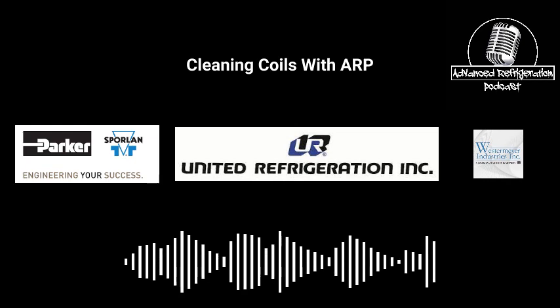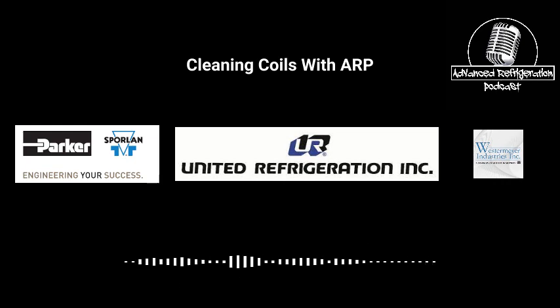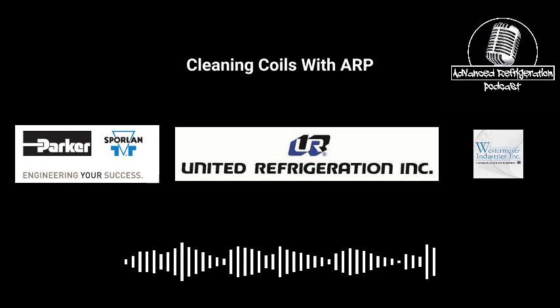I think on service calls, especially in the summertime and the beginning of it, everybody should be checking the controller, checking the head pressure to make sure it isn't super high for what it is, or that there aren't issues with fan motors. In the springtime, when everybody's slower and trying to get some work, that's your time, man. Find those. You're there for a dumb call. Go check the condensers. See how many condenser fan motors are out.